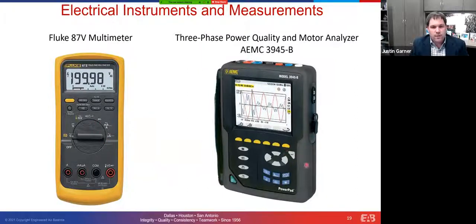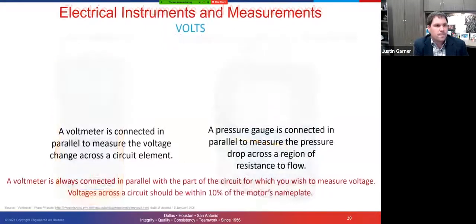Another thing that we do use on occasion, but not very often on the TAB side, is a three-phase power analyzer. If you have to measure power directly, and we do have to do that sometimes, you're going to need a device like this. It essentially measures all three phases of voltage and potentially even the neutral, as well as all three amperages at the same time. And it gives you a full picture of the power that's feeding a particular piece of equipment. And so, like I said, it's useful, but it's not something that would be used every single day.